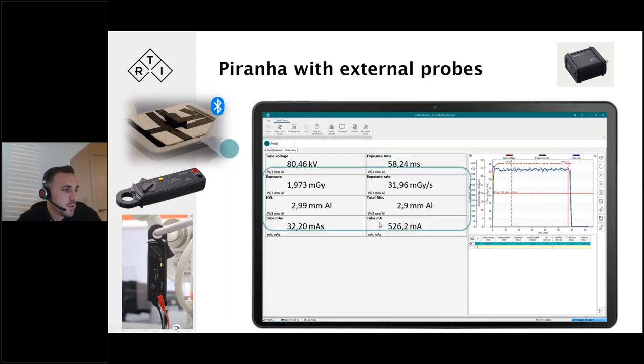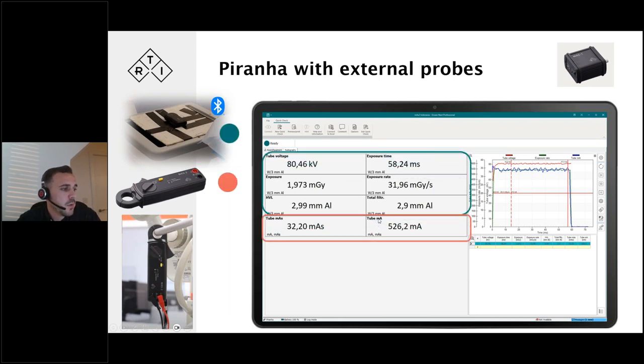In this example, just to illustrate, we have them both together, so that you can get the X-ray output measured by the Piranha in the X-ray beam, and you can use an external probe to measure, for example, tube mA and tube mAs, and see that all in a single exposure.